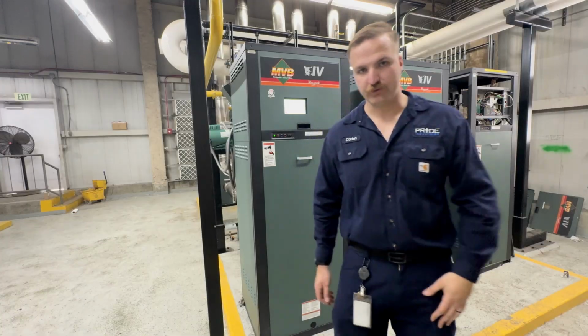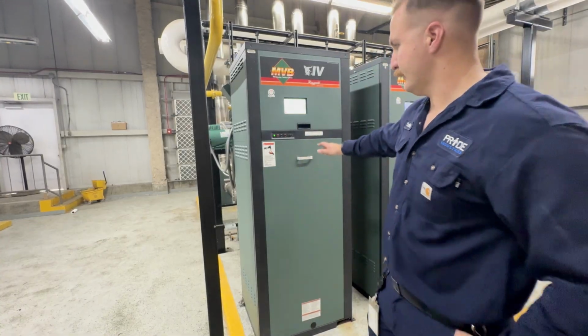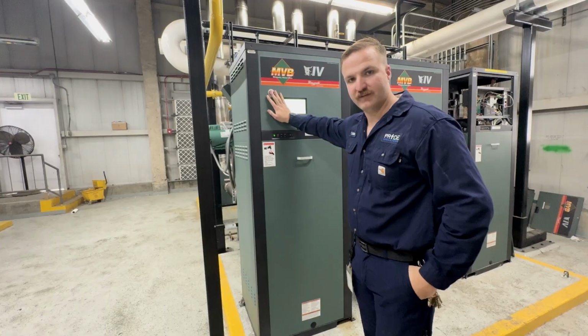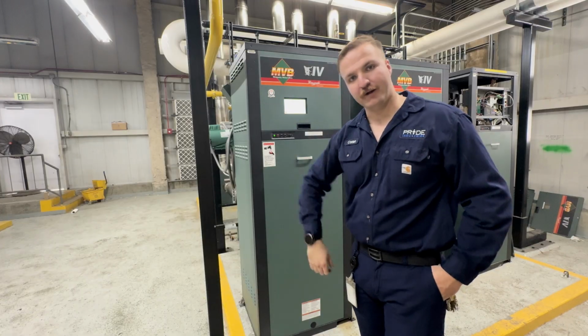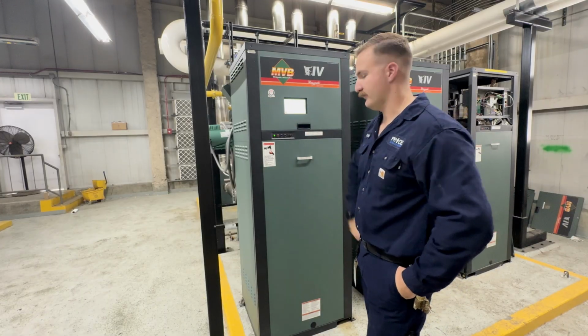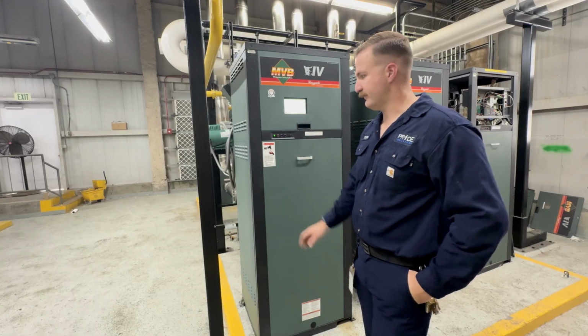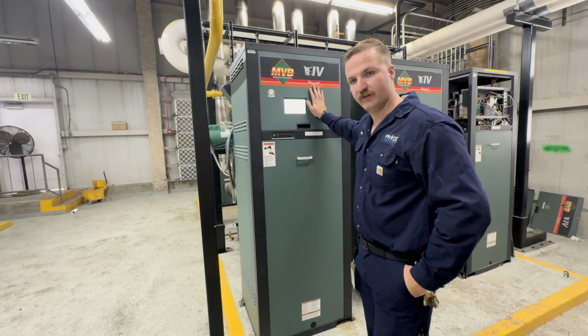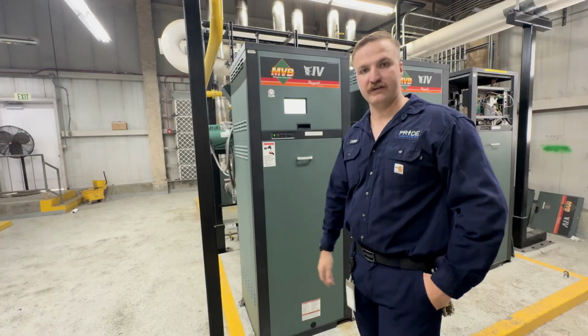All right, now that we finished reassembling the boiler and putting all the panels back on, place the BMS system back on auto, we put the boiler back on auto over the controller, and this boiler's a standby now. That's it for how to perform quarterly PMs on these boilers. Stay tuned, we're gonna release how to do an annual.